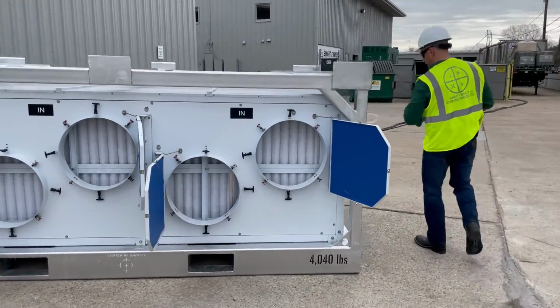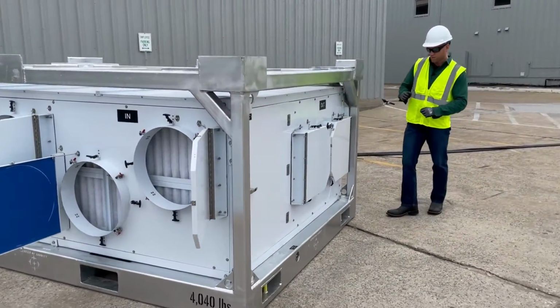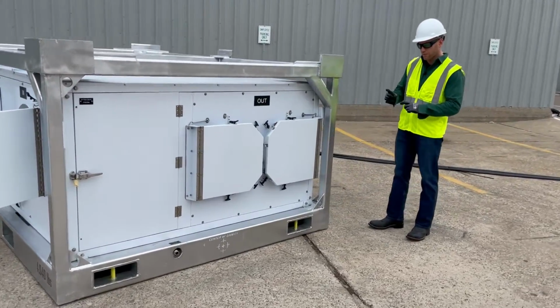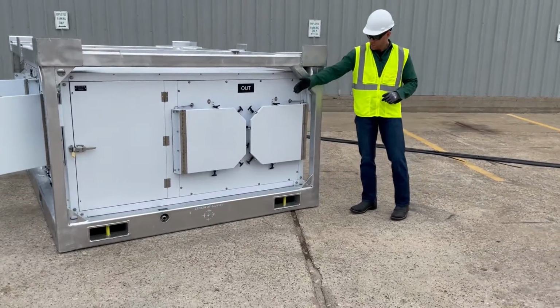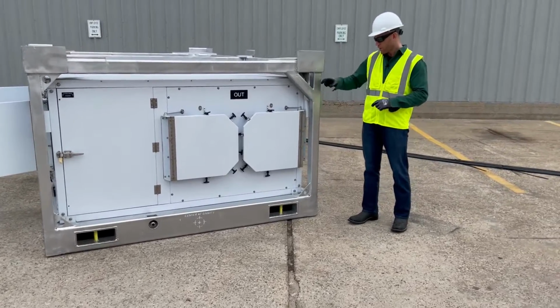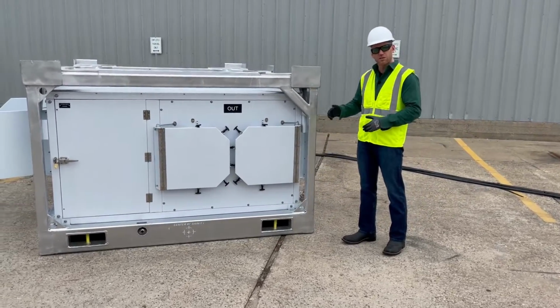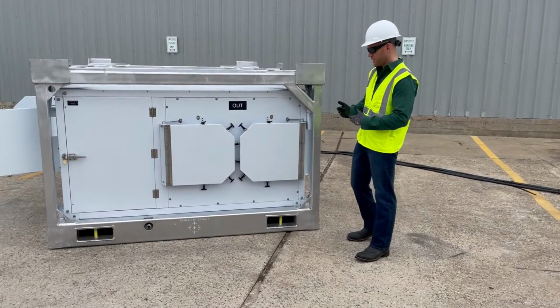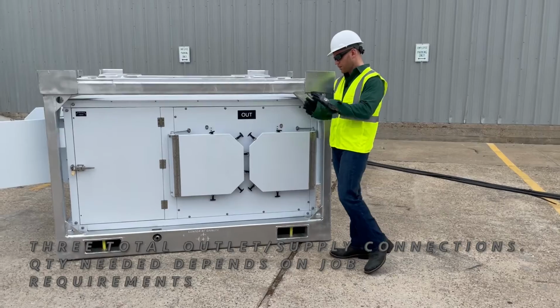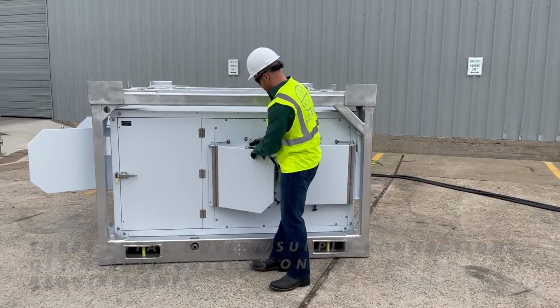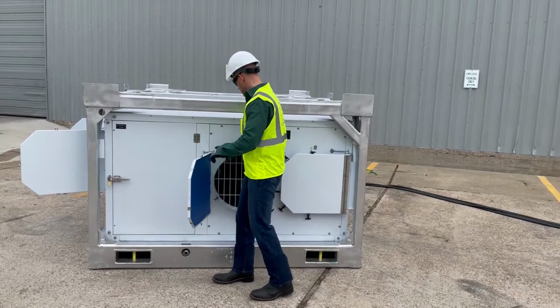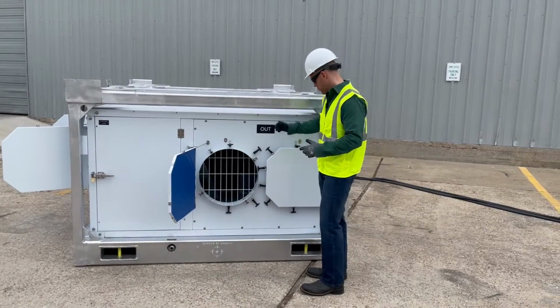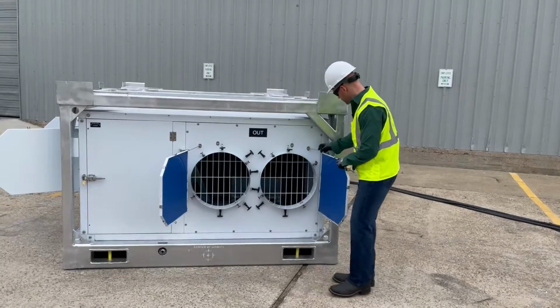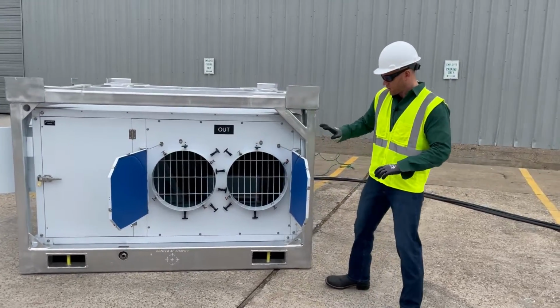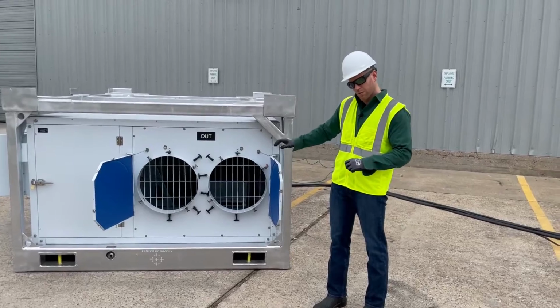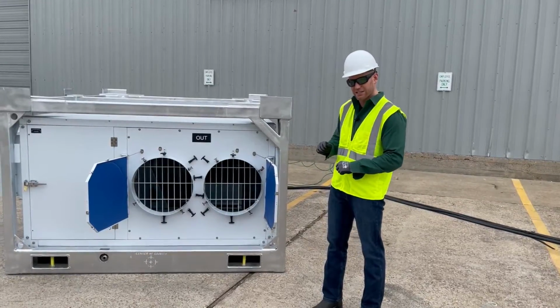Now we'll go to the outlet side of the package. On this particular model, we have 3 outlets, 2 on this side of the unit, 1 on the other. Whether we open 1, 2, or 3 ducts is going to depend upon the application, how much airflow we need at the job site or the job site layout. For this little tester, I'm going to open up 2 supply or outlet connections. You'll notice that they're clearly marked out, so you know which ones are the outlets. On this package, typically you're going to run a minimum of 2 connections, okay? But again, the job site dictates that.